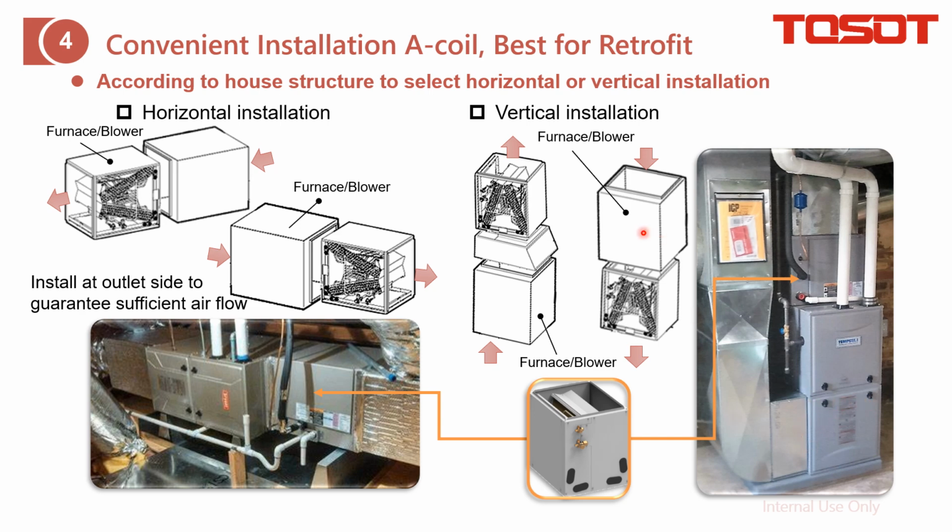And I know for the down flow, it is not that easy to modify the furnace, but we require this just to guarantee enough air volume for this furnace. And for this installation, it does not follow our requirement. Do you know what it is?